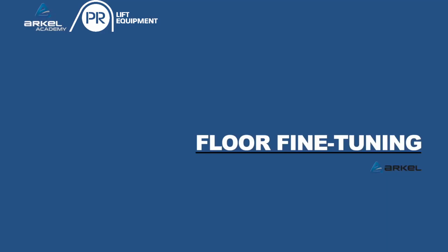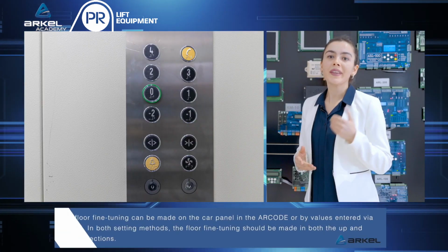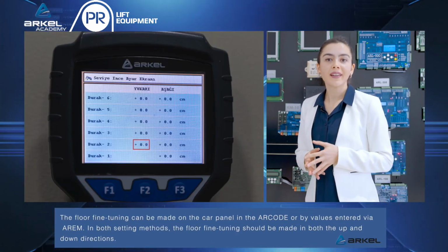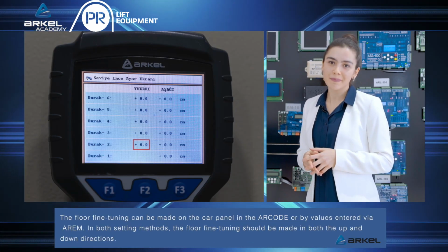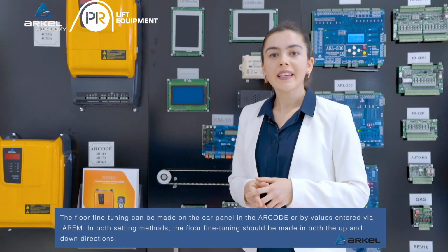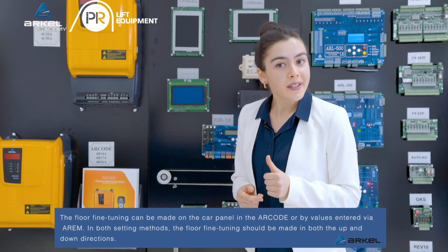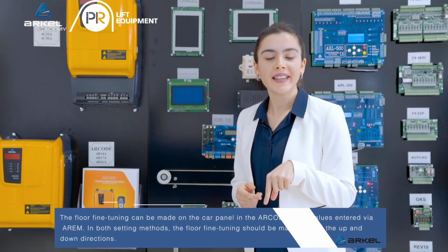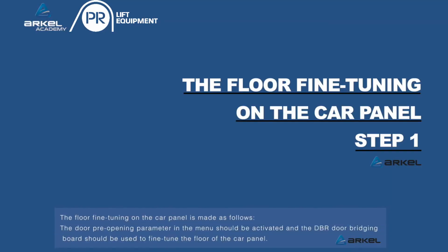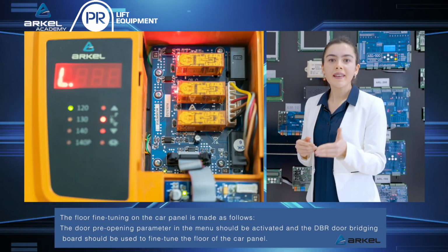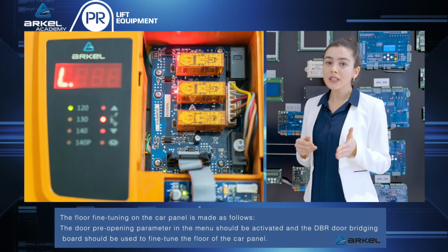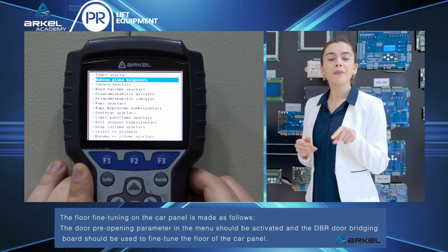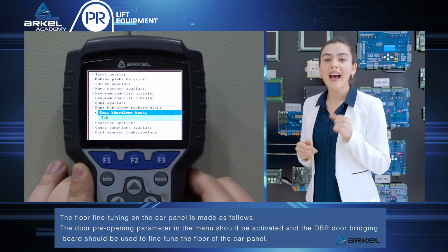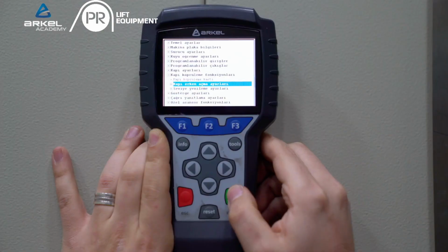Floor fine-tuning. The floor fine-tuning can be made on the car panel in the Arcode or by values entered via AREM. In both setting methods, the floor fine-tuning should be made in both the up and down directions. The floor fine-tuning on the car panel is made as follows. The door pre-opening parameter in the menu should be activated, and the DBR door bridging board should be used to fine-tune the floor of the car panel.